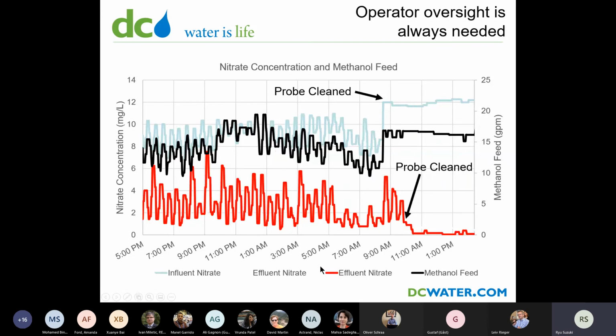And just finally, I might be going over my time limit, but no matter how robust your control system is, you're always going to need somebody watching over it. Even though we've been mostly talking about the nitrification aeration controller, this is our methanol control using nitrate probes. If you don't stay on top of the cleaning, after a while the probes are just going to start getting these crazy numbers. And you see that once the probes are clean, the readings stabilize.